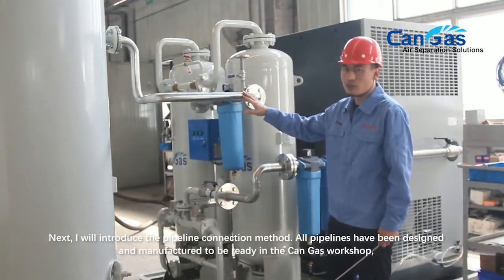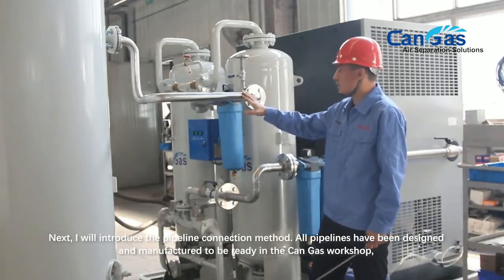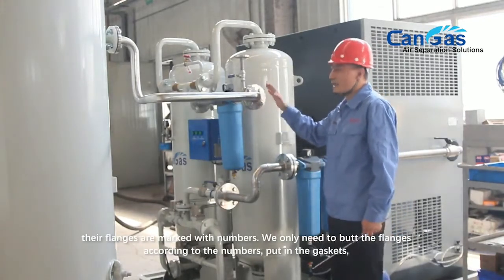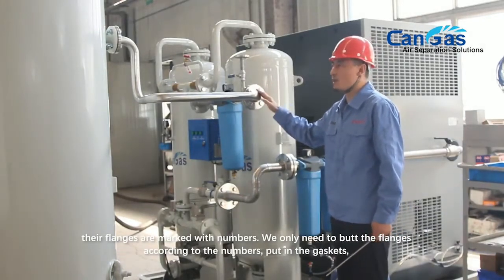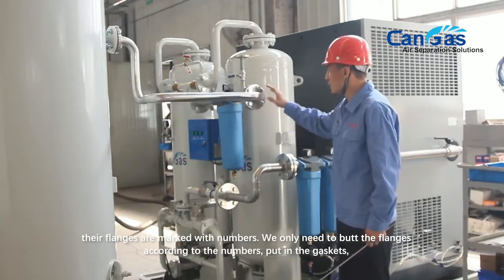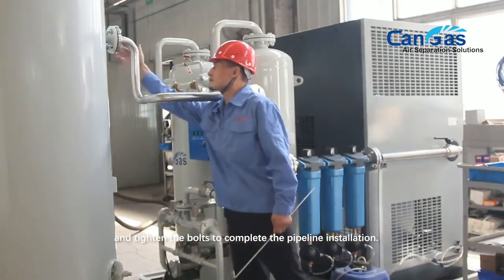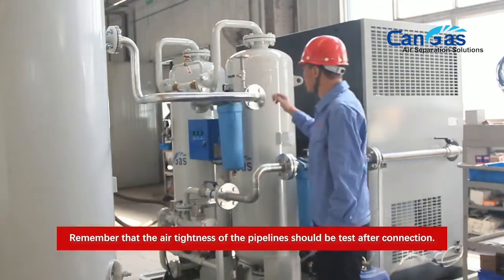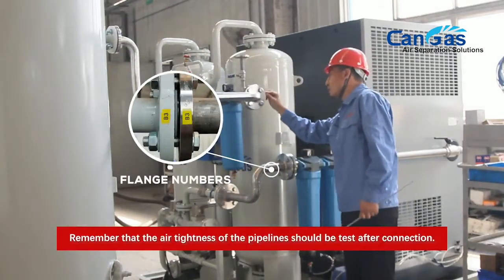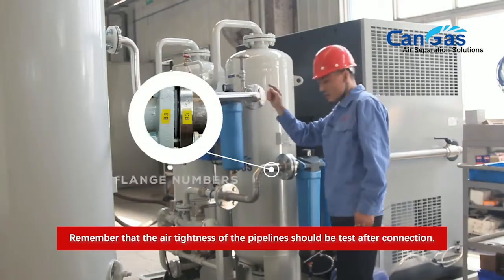All pipelines have been designed and manufactured to be ready in the CanGas workshop. Their flanges are marked with numbers. We only need to butt the flanges according to the numbers, put in the gaskets, and tighten the bolts to complete the pipeline installation. Remember that the air tightness of the pipeline should be tested after connection.